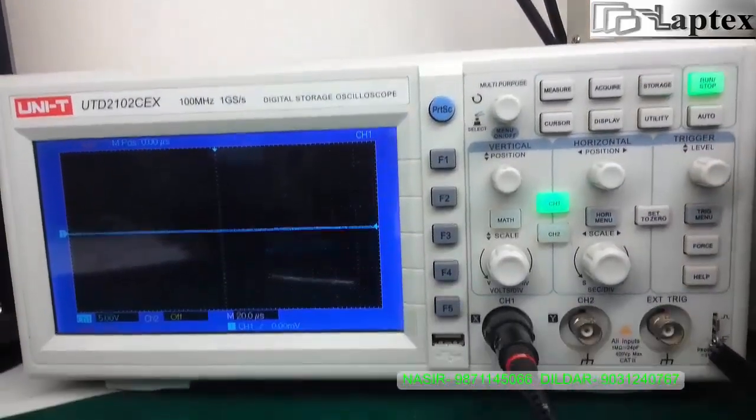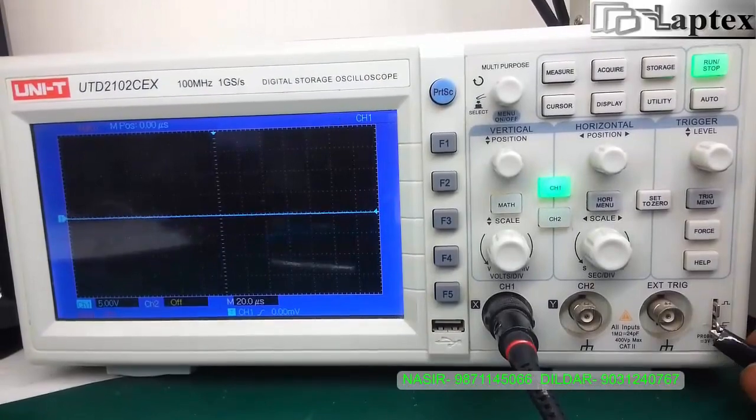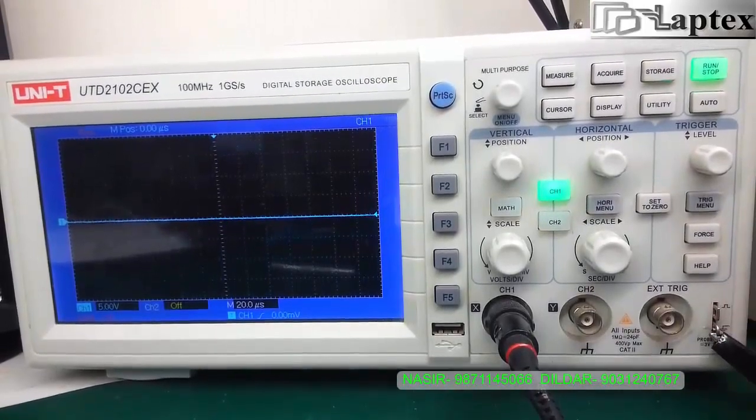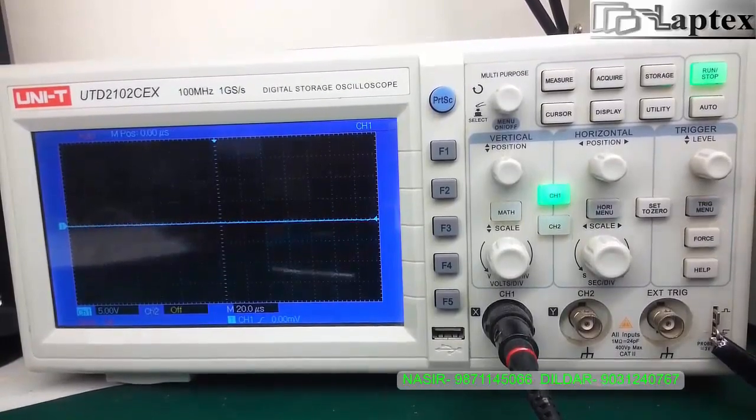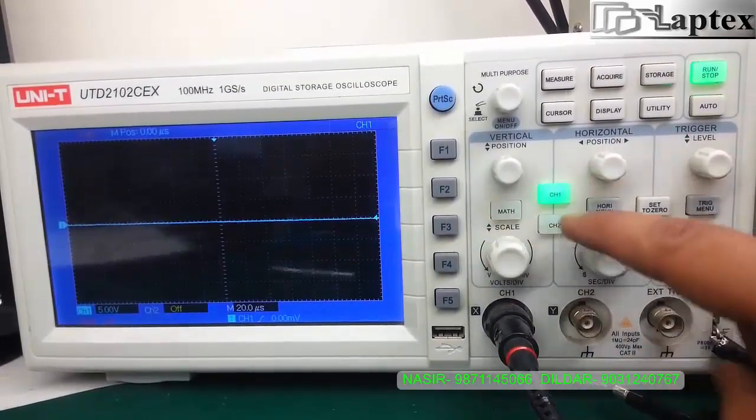Let me tell you one of the important points. You can see here there is a square wave pin and a ground pin, and you have two settings in the probe: a 1x setting and a 10x setting.